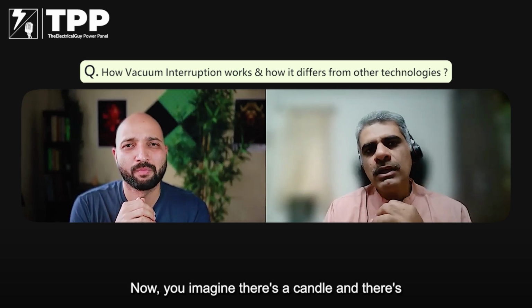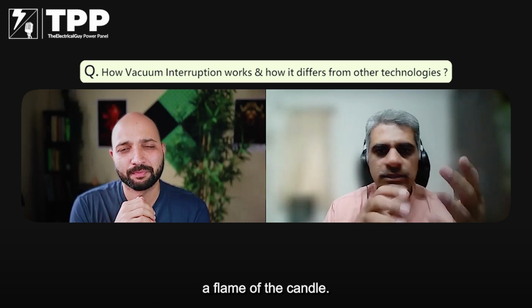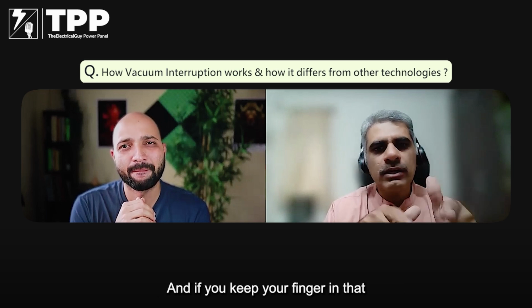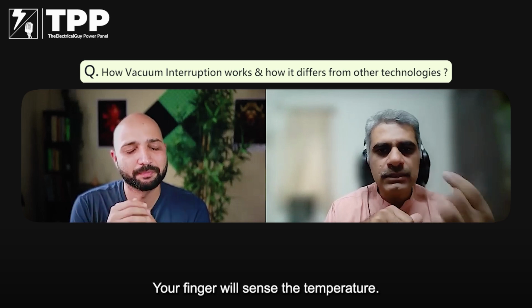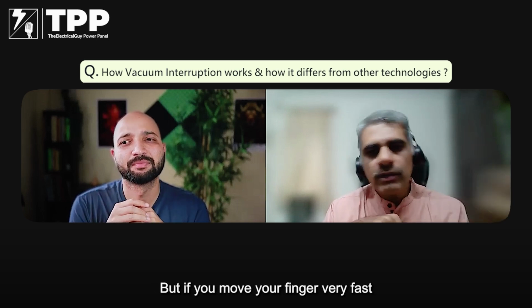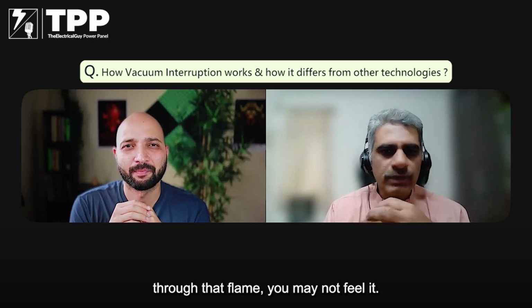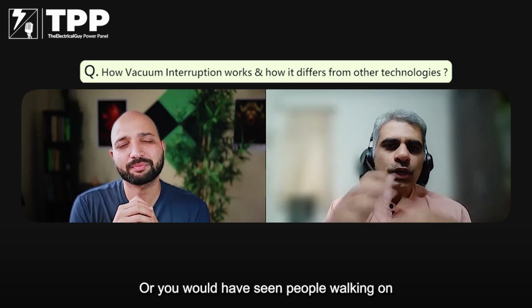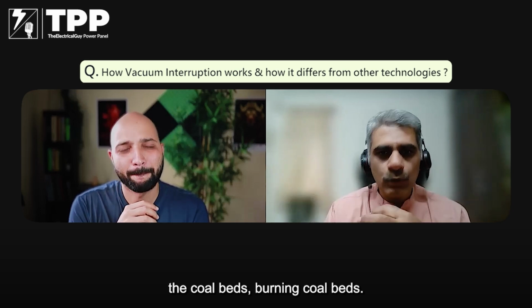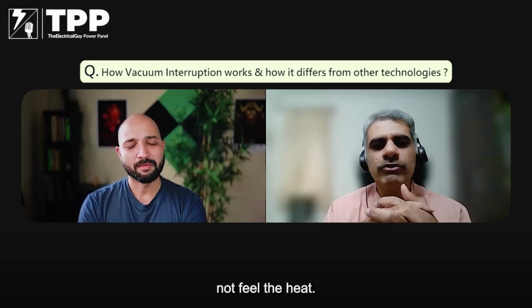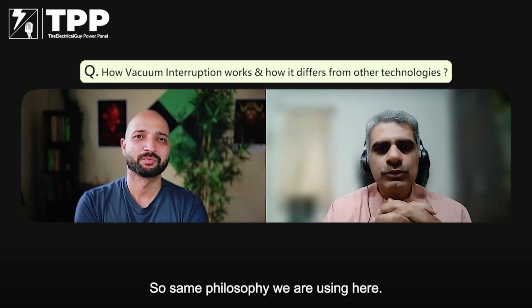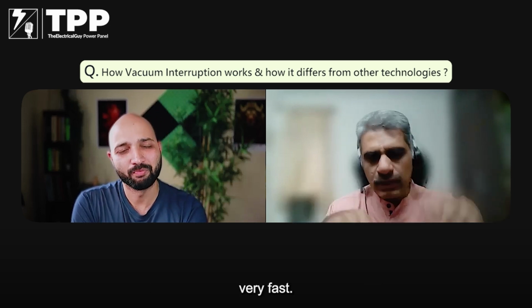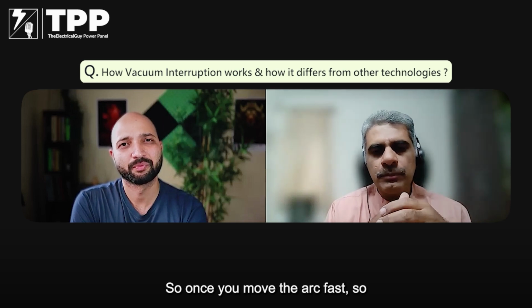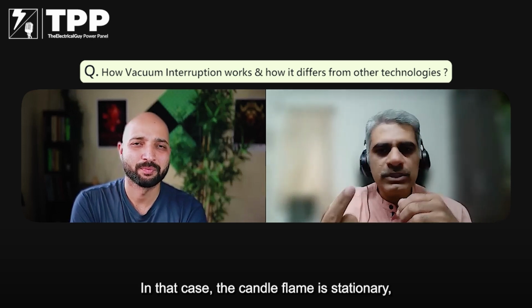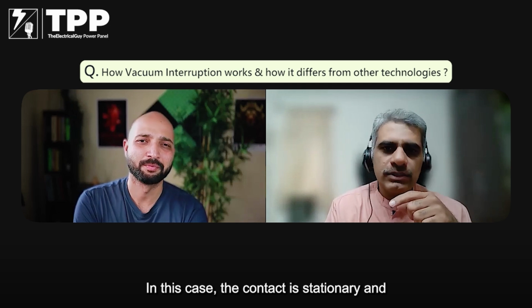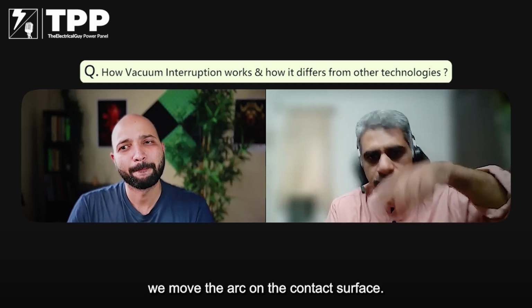Now imagine there's a candle and there's a flame of the candle, and if you keep your finger in that flame, obviously you'll get hurt. Your finger will sense the temperature. But if you move your finger very fast through that flame, you may not feel it. Or you would have seen people walking on burning coal beds. If you walk very fast, your feet would not feel the heat. So the same philosophy we are using here. What we do is we move the arc very fast. So it's the reverse: in that case, the candle flame is stationary and you move your finger. In this case, the contact is stationary, and we move the arc on the contact surface.